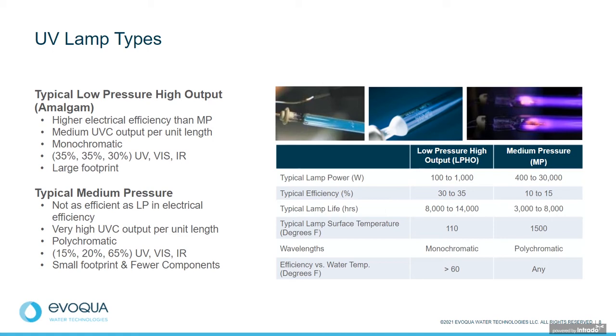in a reactor. A medium-pressure lamp is not as efficient. It's only 15% efficiency in the germicidal range compared to the input power, but it's got a very high UVC output per unit length of lamp and is polychromatic. The advantage of medium pressure is in the number of components and the space. A medium pressure system might have one lamp compared to a low pressure output lamp system that might have 25 or 30 lamps. So you can have one typical medium pressure lamp replace a number of low pressure lamps. So smaller footprint, fewer components. So there are advantages to both.